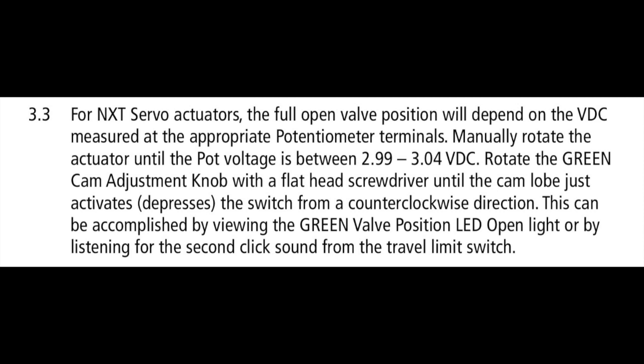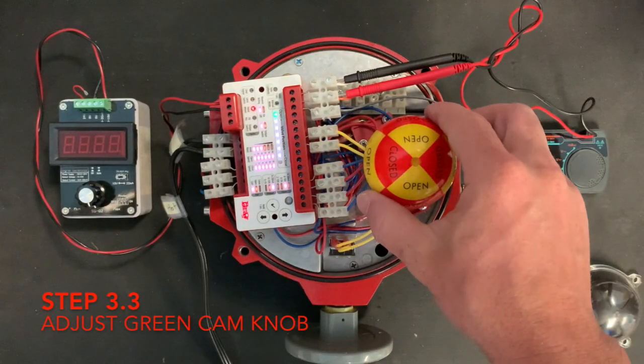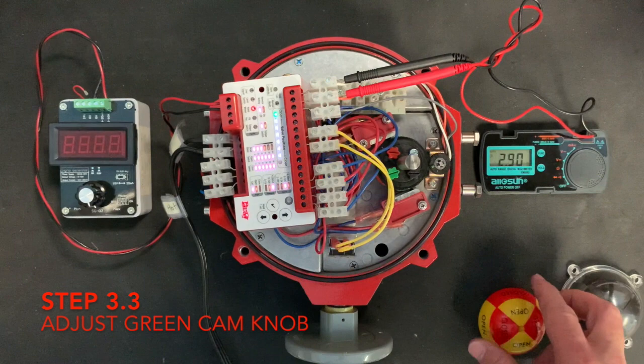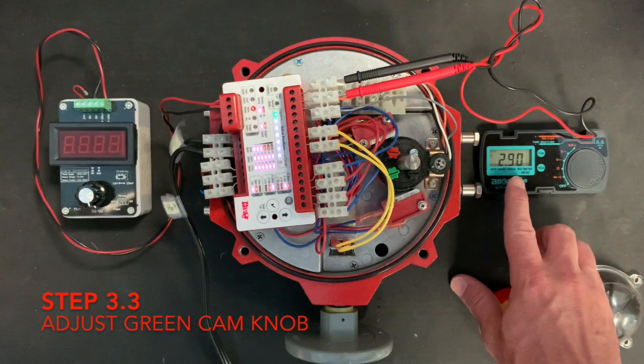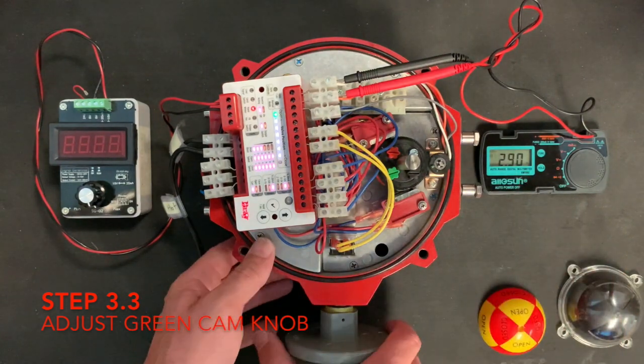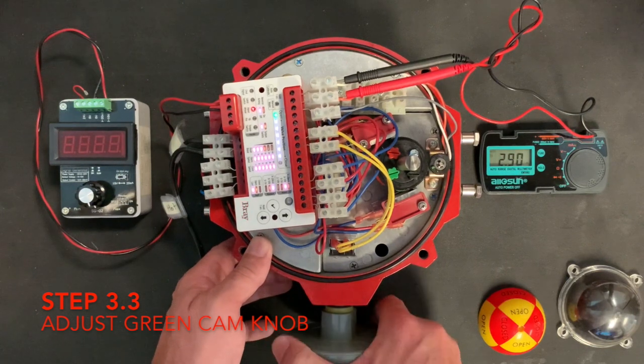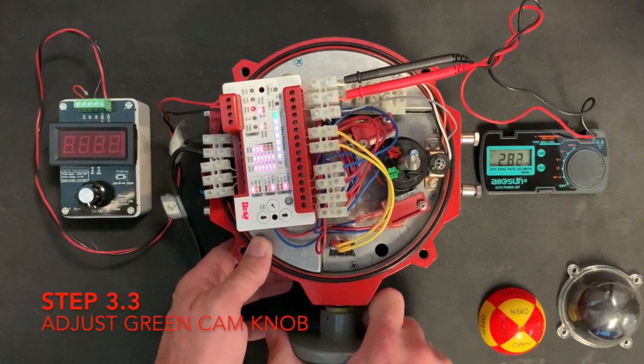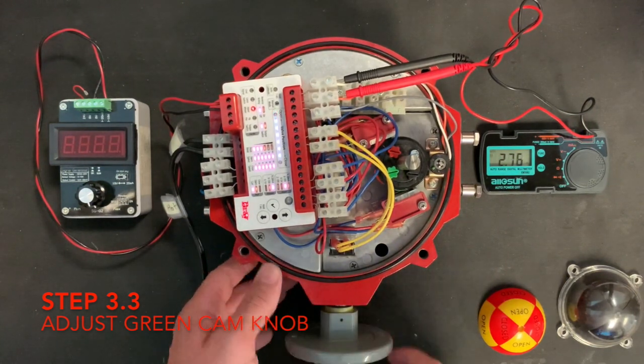For NXT servo actuators, the full open valve position will depend on the VDC measured at the appropriate potentiometer terminals. Manually rotate the actuator until the pot voltage is between 2.99 to 3.04 VDC.